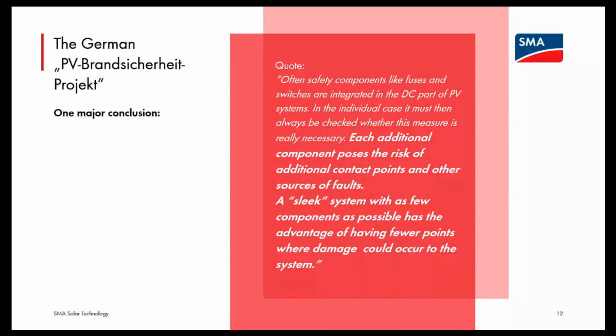Is there a benefit? And I think this is partially answered by a very important sentence in that study that Harry just presented. And I'd like to read the quote to you. It says, often safety components like fuses, switches, are integrated in the DC part of the PV systems. In the individual case, it must then always be checked whether this measure is really necessary. And then it goes on, each additional component poses the risk of additional contact points and other sources of faults.